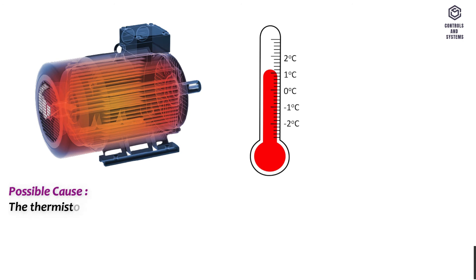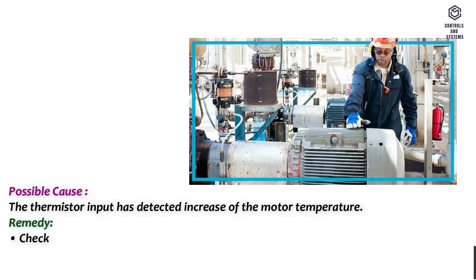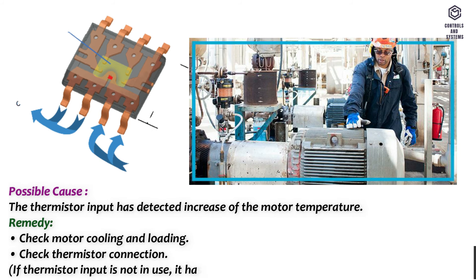Fault code 29 – Thermistor fault. Possible cause: the thermistor input has detected an increase in motor temperature. Remedy: check motor cooling and loading, check thermistor connection. If the thermistor input is not in use, it must be short-circuited.